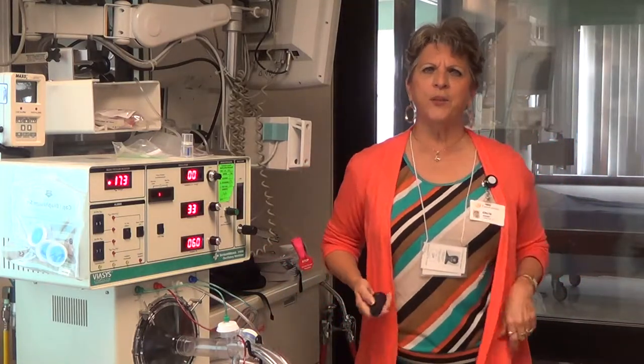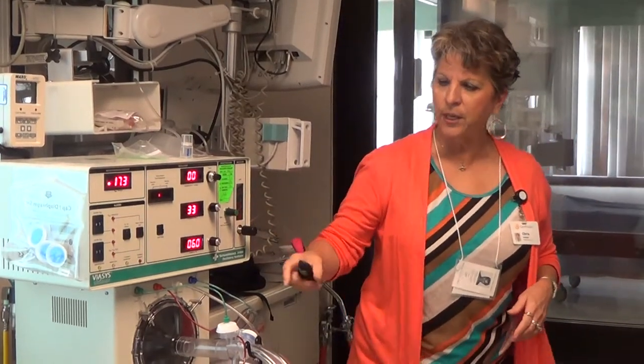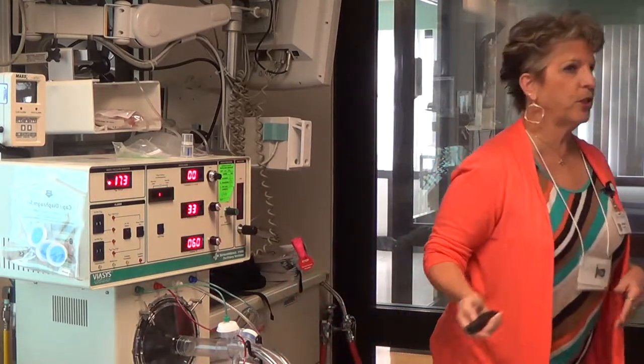Okay. Was it you that emailed me these questions? Yeah. Okay. So the more flow I have going through here, the more distended that little mushroom valve gets, the more resistance it creates, the more mean airway pressure I get.